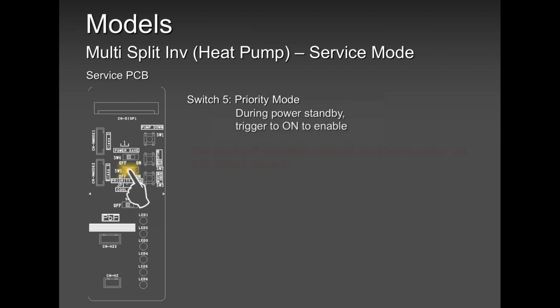Priority mode. What is priority mode? Priority mode is given to the operation of the indoor unit with the highest capacity. So what happens if there is an 18,000 and a bunch of 9,000s? If this switch is activated, the 18,000 unit has the priority to change modes, even if the mode was in the opposite mode. So let's say the person with the 9,000 came in first into the house or into the office and turned the unit to heating. You that own the 18,000 go in, you can change it from heating to cooling, only if you have activated that SW5 button. Okay, that's all about the priority mode.